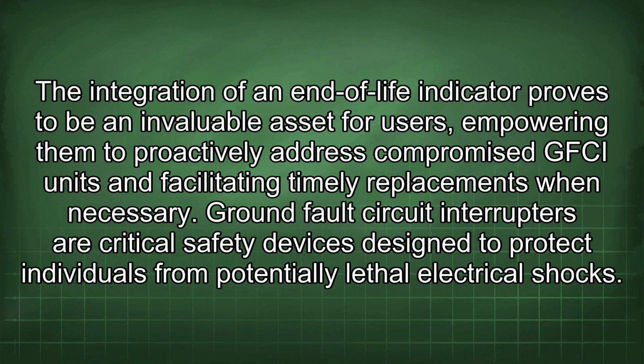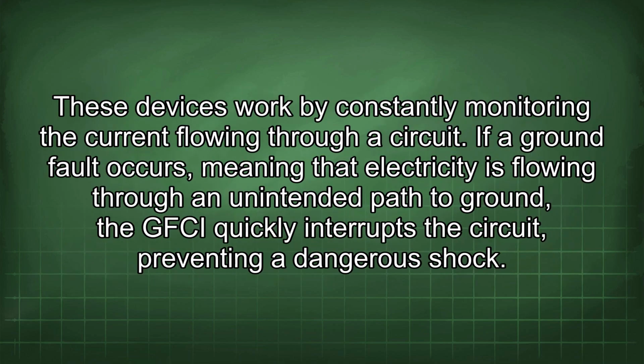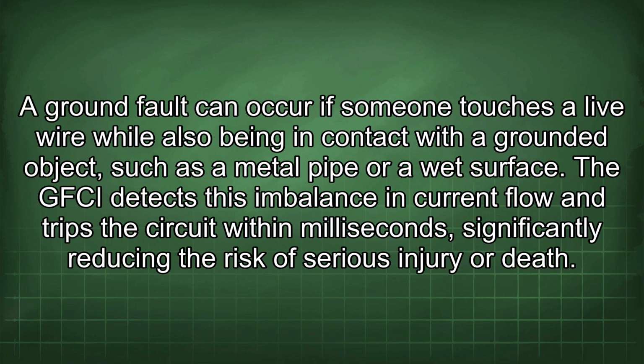Ground fault circuit interrupters are critical safety devices designed to protect individuals from potentially lethal electrical shocks. These devices work by constantly monitoring the current flowing through a circuit. If a ground fault occurs, meaning that electricity is flowing through an unintended path to ground, the GFCI quickly interrupts the circuit, preventing a dangerous shock. A ground fault can occur if someone touches a live wire while also being in contact with a grounded object, such as a metal pipe or a wet surface. The GFCI detects this imbalance in current flow and trips the circuit within milliseconds, significantly reducing the risk of serious injury or death.